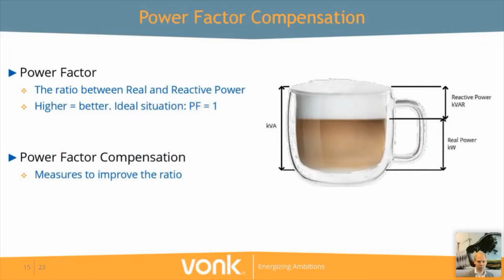When addressing power factor compensation, I first want to explain a bit about what power factor actually is. Power factor is the ratio between the real power, the power that you're actually consuming in your application, and reactive power caused by harmonics and phase shift. The higher the ratio, the better it is, which means the more real power and the less reactive power you have. In an ideal situation, you only have real power and no reactive power at all, so a power factor of 1.